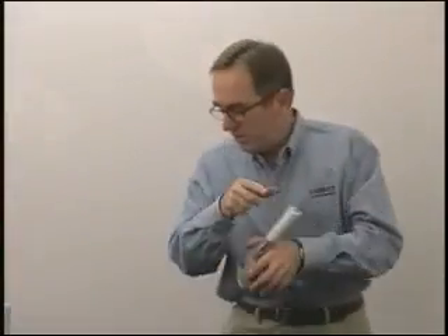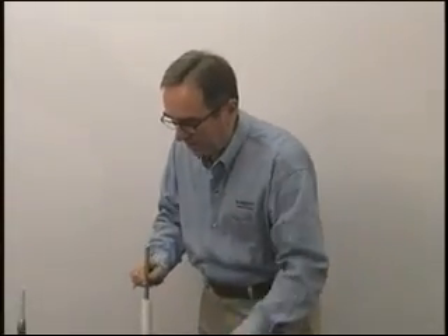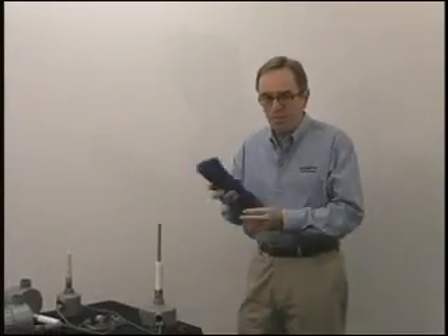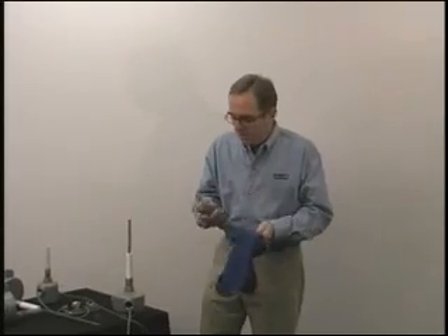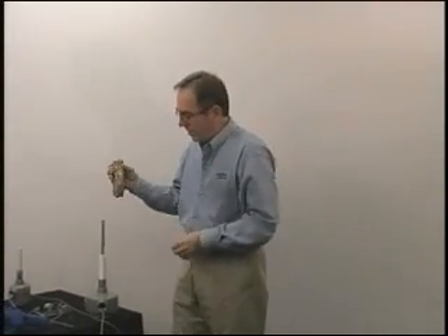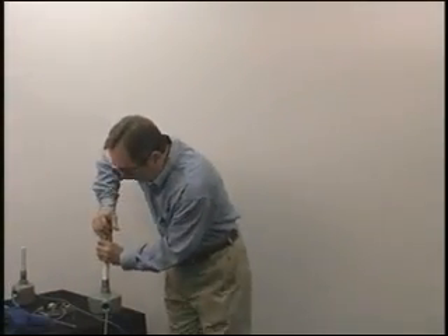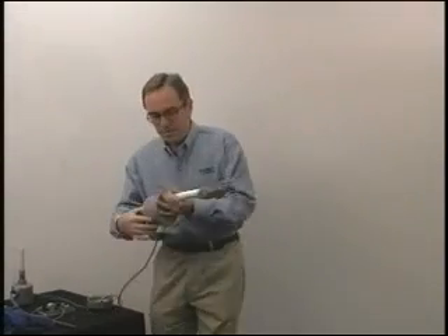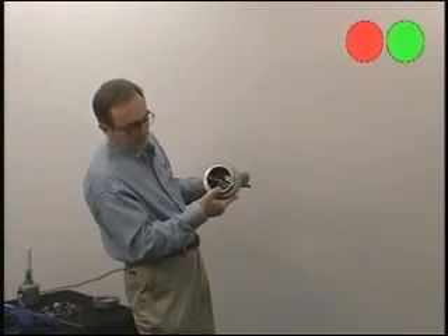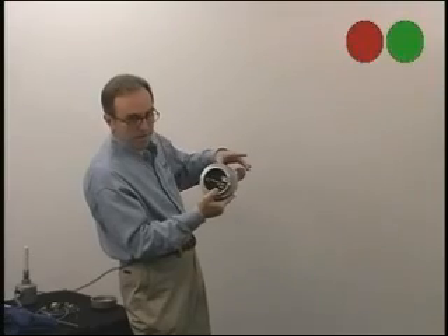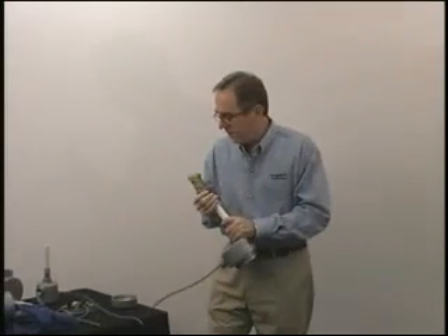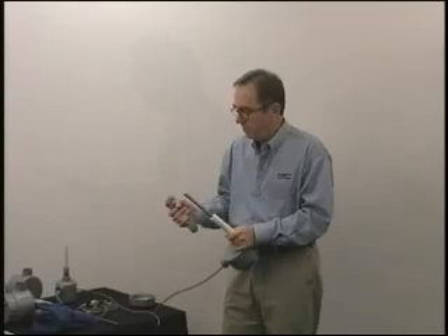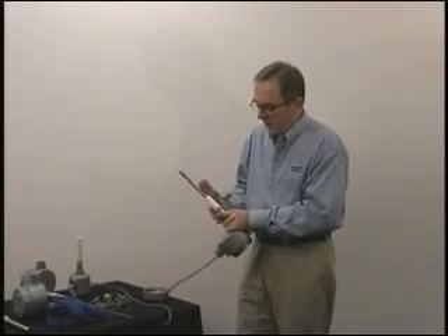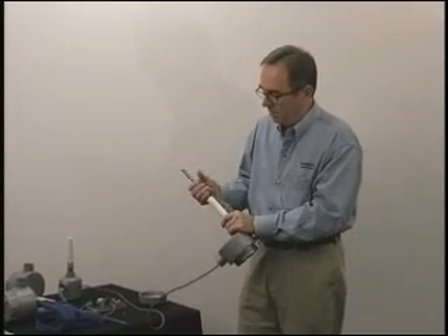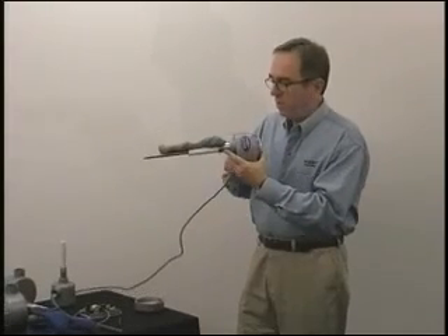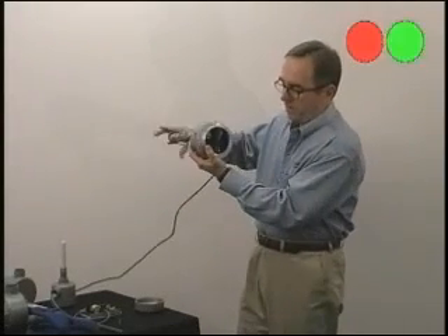Our claim to fame with this unit is that it can withstand a pretty significant amount of material buildup on the probe without having to recalibrate it. To demonstrate that, I have a pound of modeling clay. Going to put it on the probe, completely cover it up, and you can see the probe will still work. The high frequency RF signal gives it the ability to see through the product buildup on the probe. If you have a non-conductive buildup on the probe, from the grounded vessel wall to the probe, it'll still work.